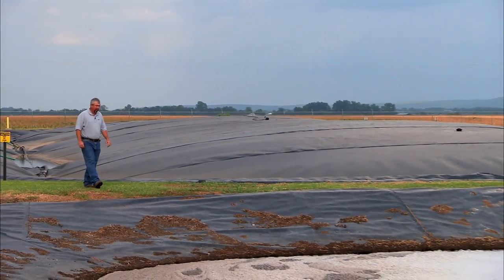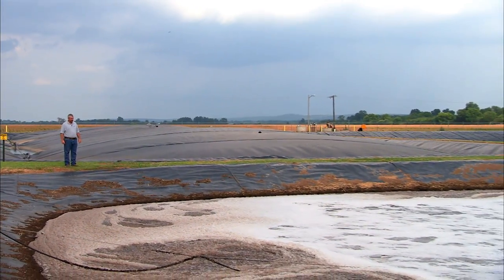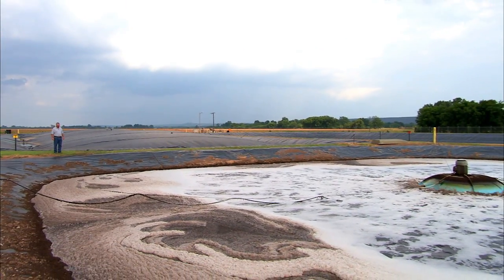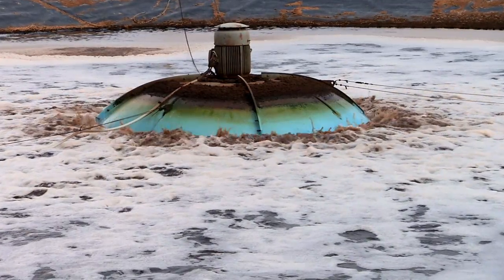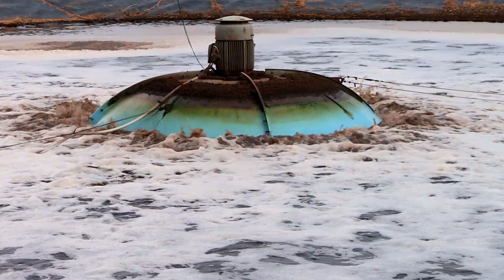The irrigation water is a good source of nitrogen. After stage one — our digester — the effluent gravity feeds over into our aeration basin. As the name implies, it changes our process from anaerobic in the digester to an aerobic system in the aeration basin. It adds oxygen to promote a different set of microbial growth, which further breaks down the solids.